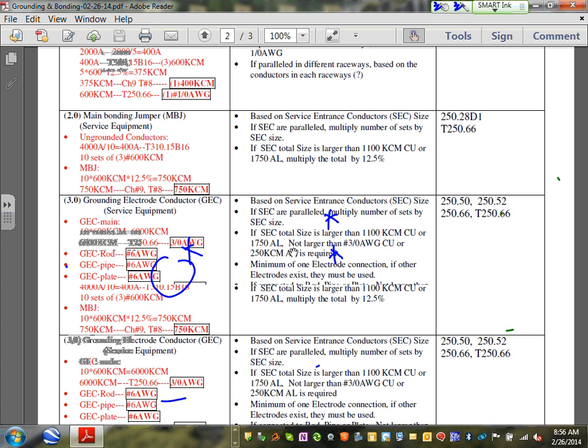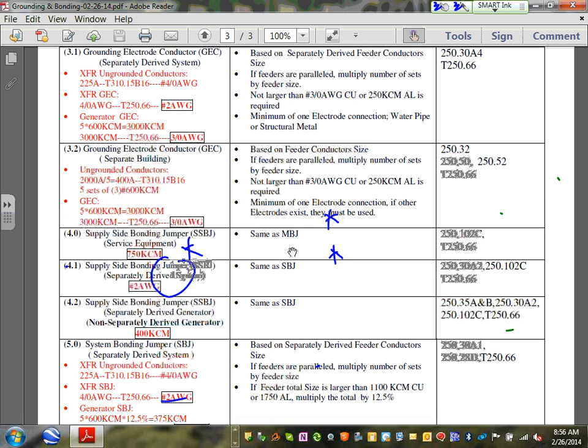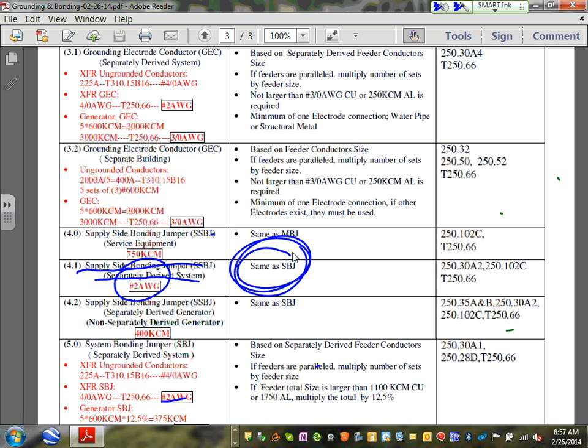Very easy, guys. Here's 4.1. Can you guys see, no calculation needed? It tells you, hey, by the way, it's called supply side bonding jumper. Oops, I'm sorry, 4.1, right underneath it. It's called supply side bonding jumper at the separately derived system. It's number 2, and it's identical to the system bonding jumper. Don't do any calculation. Size it the same as a system bonding jumper.